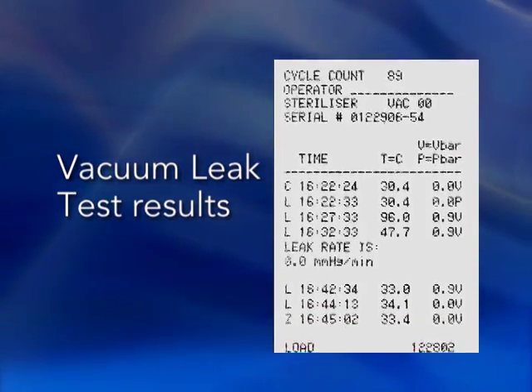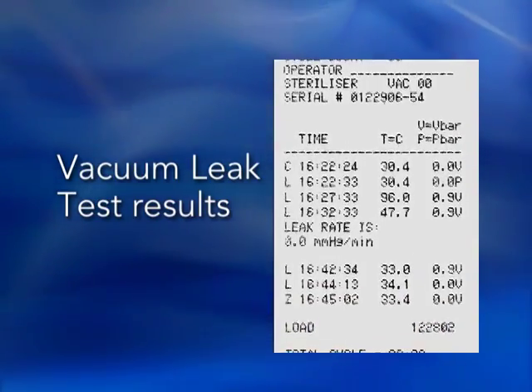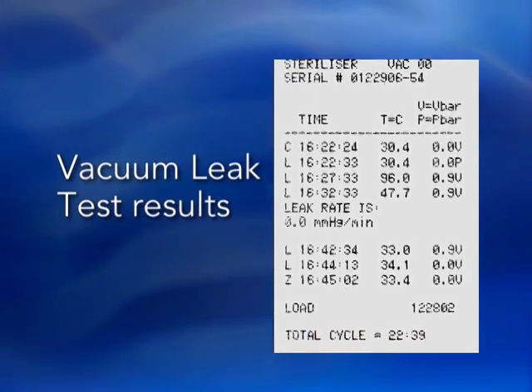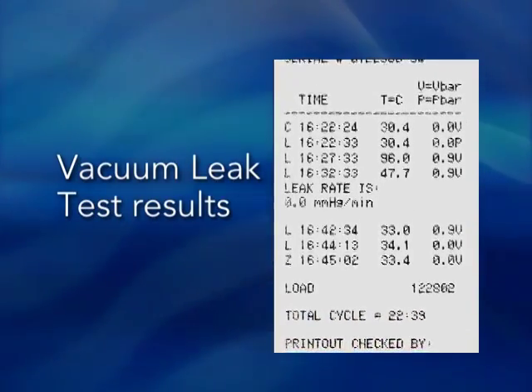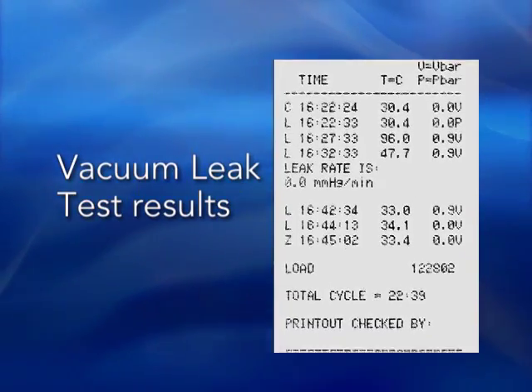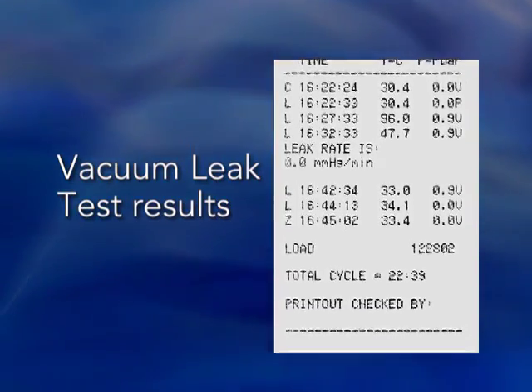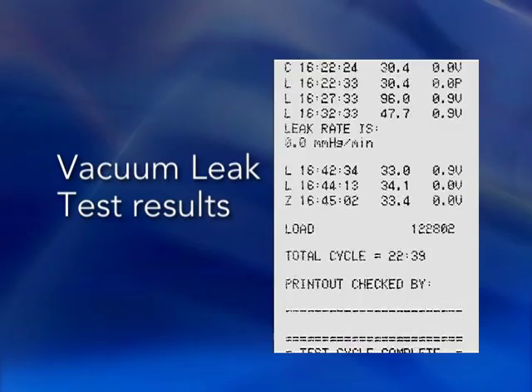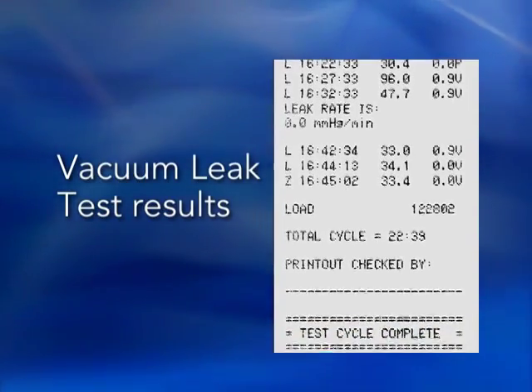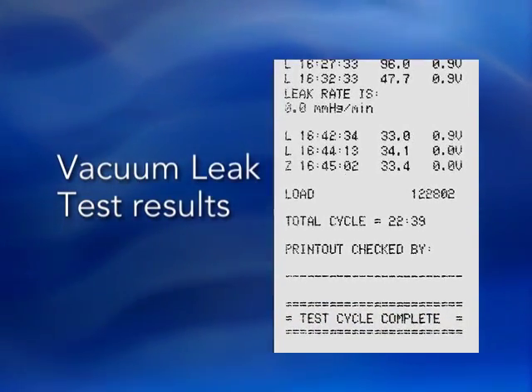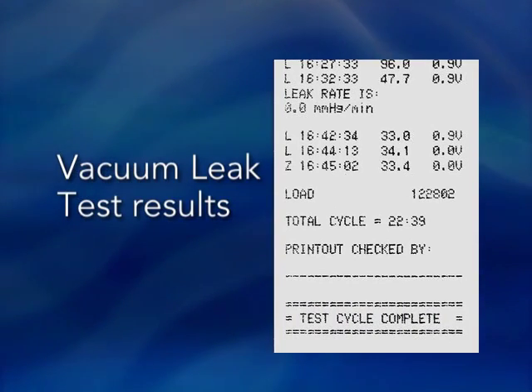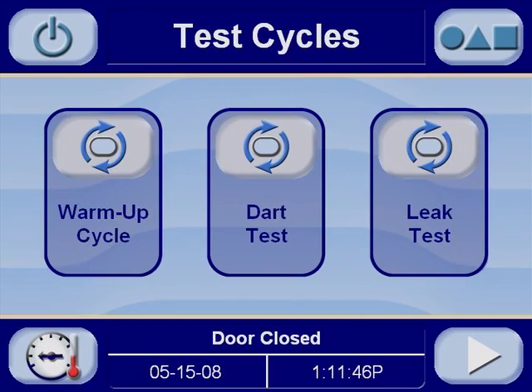A leak rate of less than 1 millimeter of mercury per minute is considered acceptable. Leaks greater than this need to be addressed by service or maintenance personnel who can monitor the air tightness of the system and make repairs or adjustments as needed. Only SFPP and gravity cycles should be run if the leak rate is greater than 1 millimeter of mercury. It's important to note that the vacuum leak test is not a suitable substitute for a DART or Bowie-Dick test.